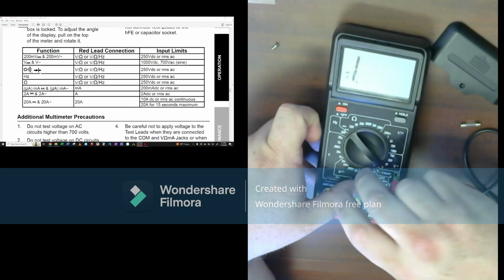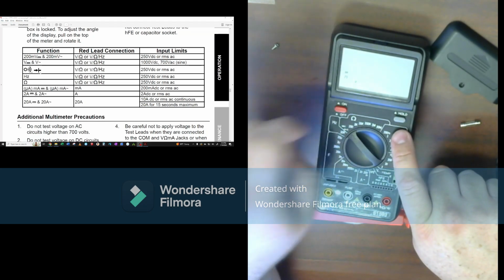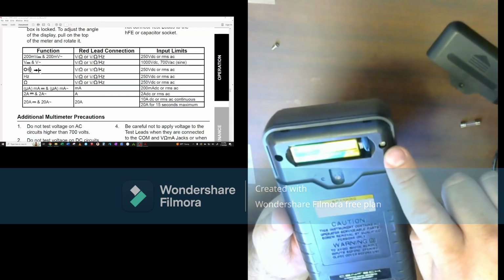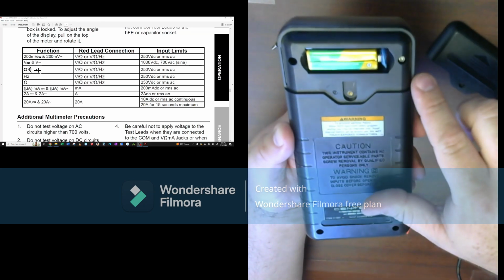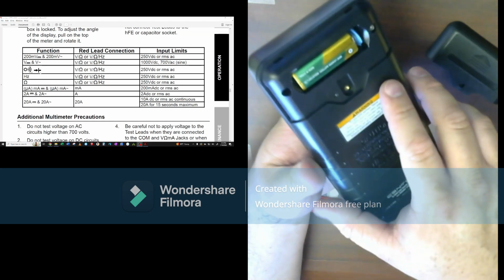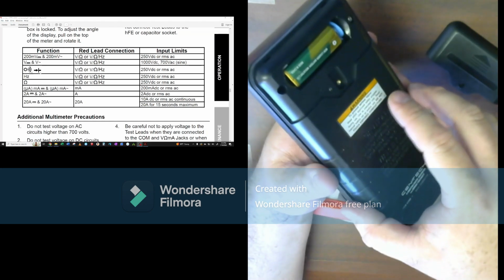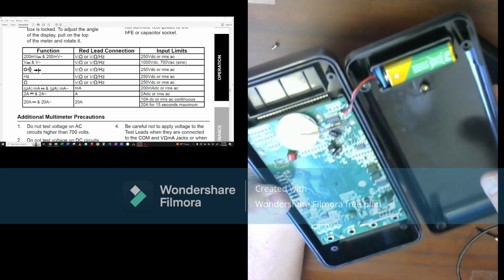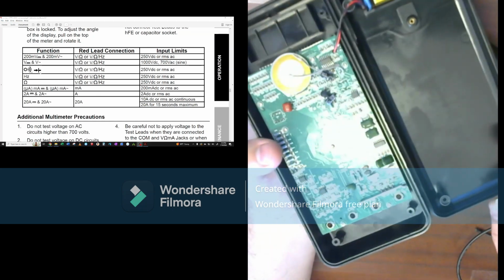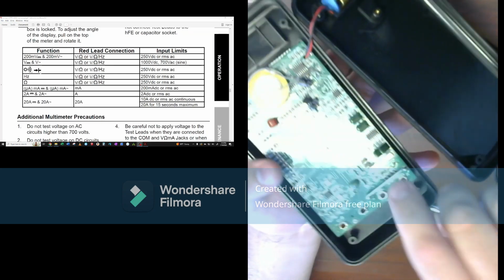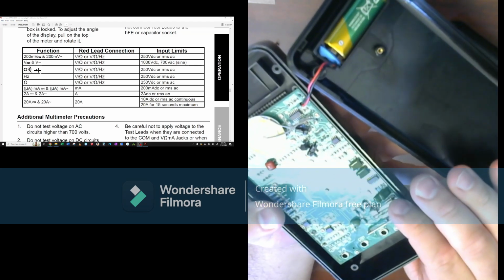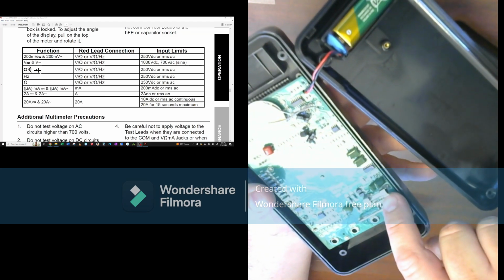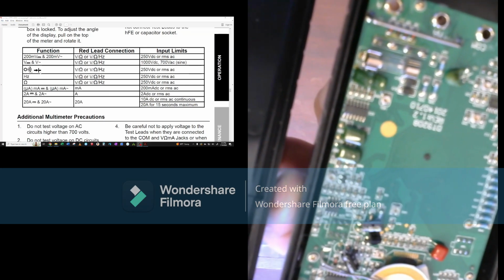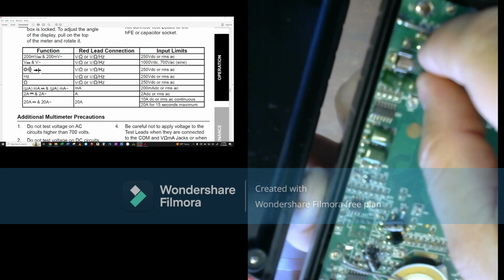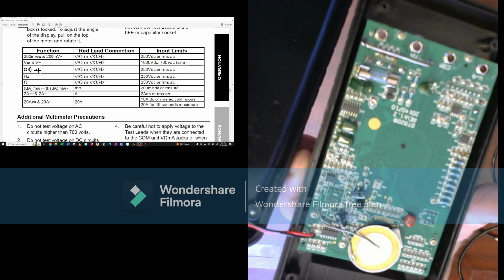Again, we'll take our probes out because it's easier to work with them out. Turn this off, flip it over. If the screws in the four corners were not already loosened, we'd loosen them, take it apart, and do these same steps. But since I never tightened these back down, I can just open this up, being careful of my battery connection, and take my fuse. In these two little prongs that are standing up right here, I can pop the fuse back into place until it connects. Make sure the metal fuse holders on the side are touching the fuse, and we now have continuity again.